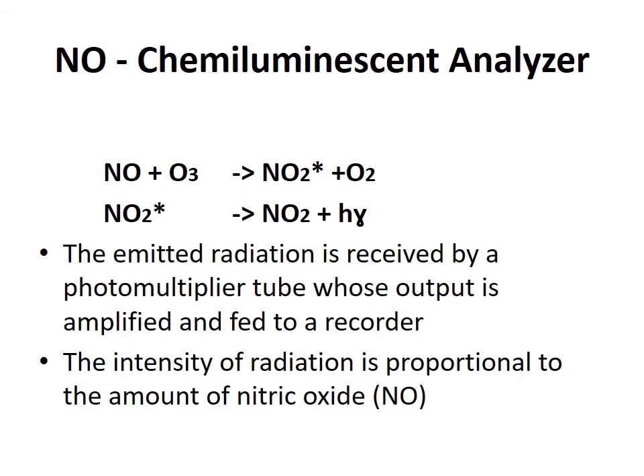The nitric oxide reacts with ozone to form nitrogen dioxide in the excited state and oxygen. The excited nitrogen dioxide reverts to the ground state, emitting radiation received by the photomultiplier tube, amplified, and fed to the recorder. The intensity of this radiation is proportional to the amount of nitric oxide.